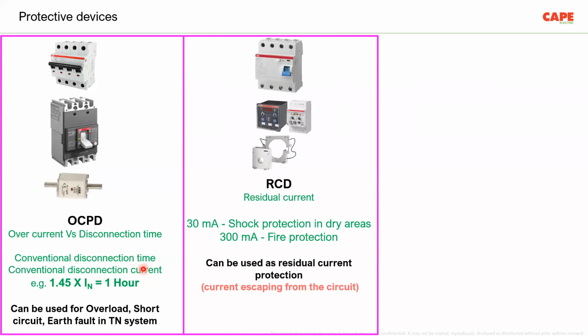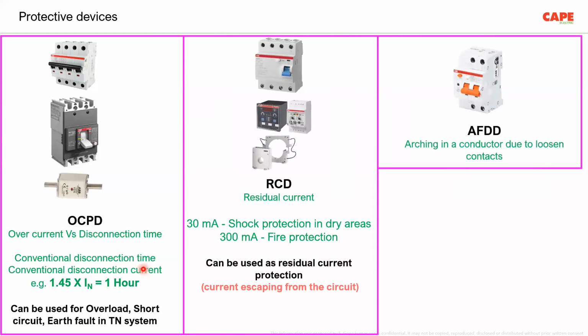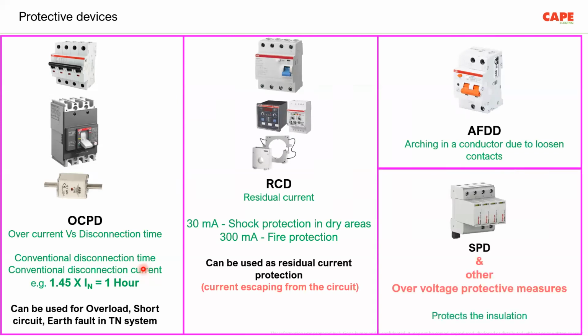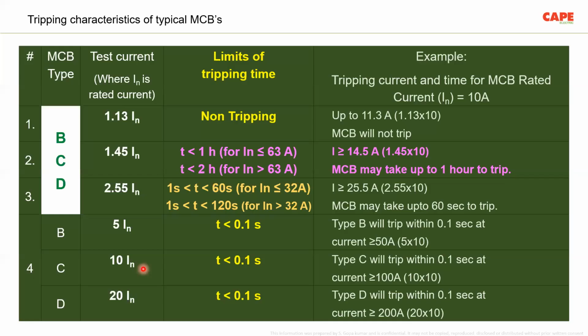Then we have protective devices such as residual current devices. We have arc fault detection devices, and we have SPDs, surge protective devices. So in our network, we have different kinds of protective devices. And if these devices are selected and erected appropriately as per the recommendation of the standards, for example, IS 732 or the upcoming National Electrical Code, you can be sure that the chance of fire or chance of accident is reduced drastically, very, very minimum.